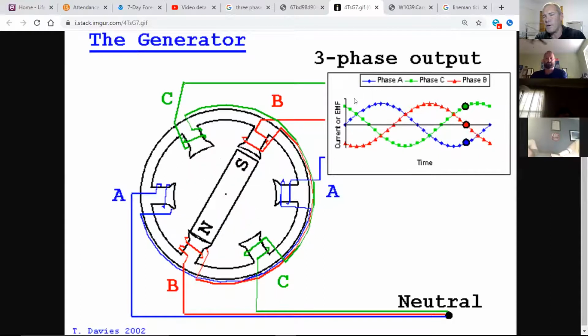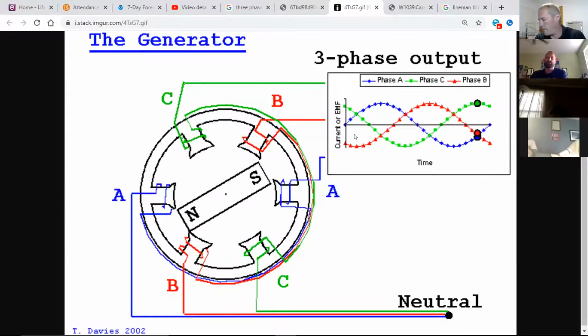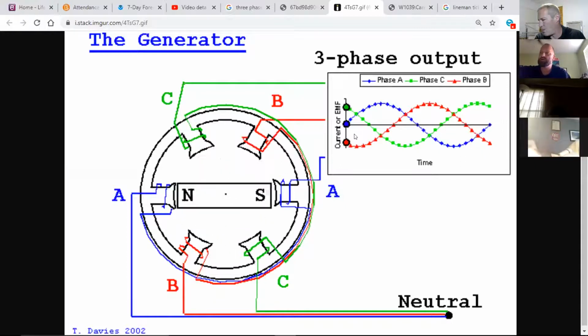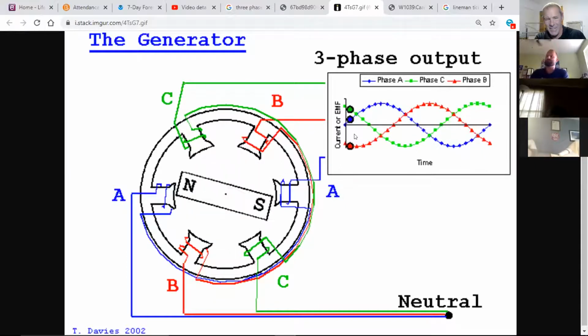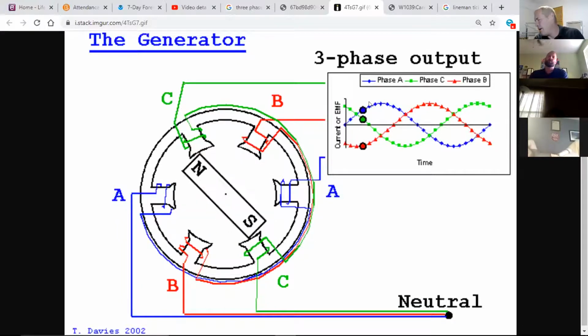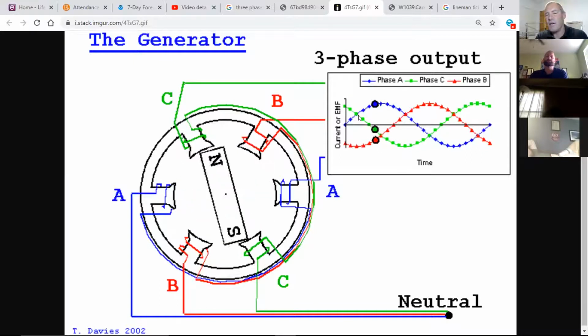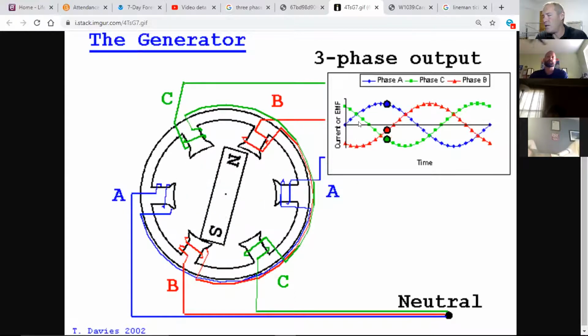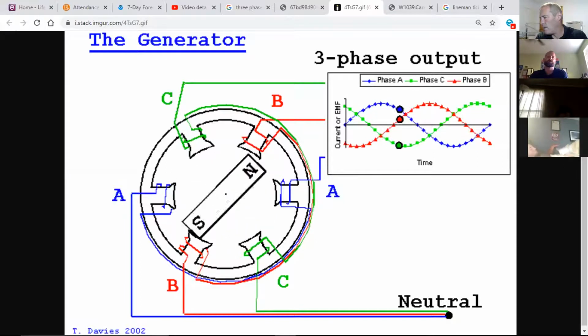Any questions there? Where did I get 12,470 from? You multiplied it by the magic number 1.7325. Right, I took the phase to ground voltage here of one phase and multiplied it by 1.7325 to get my three-phase. Now that's a combination of A and B, or B and C, or A and C. Any combination of any two, or the combination of all three.